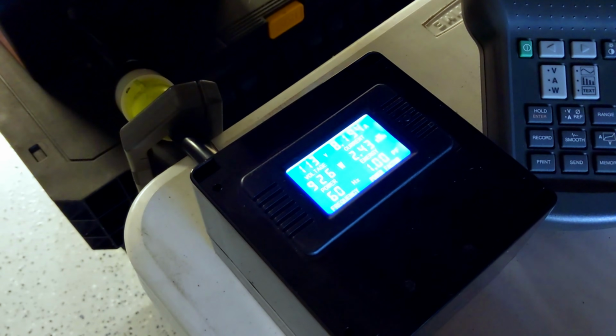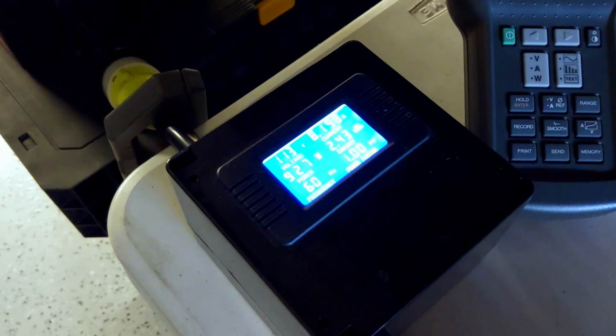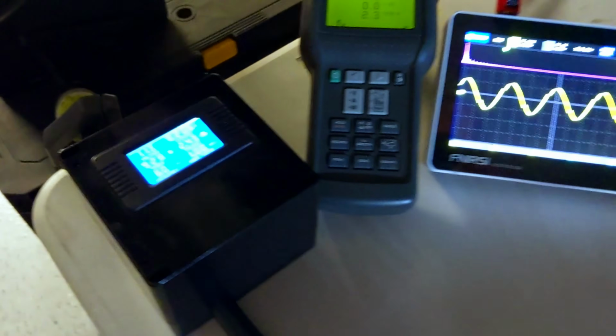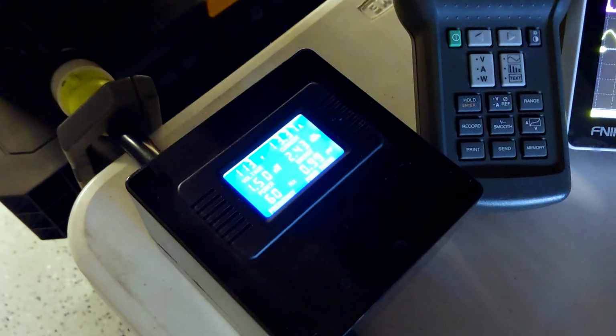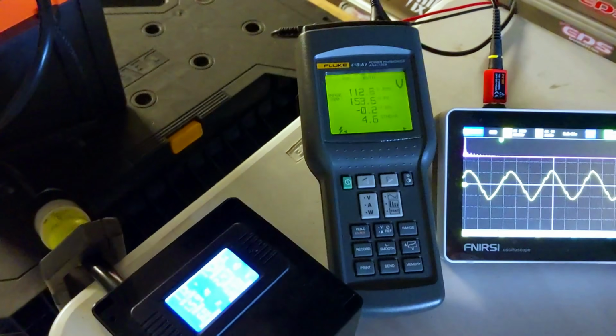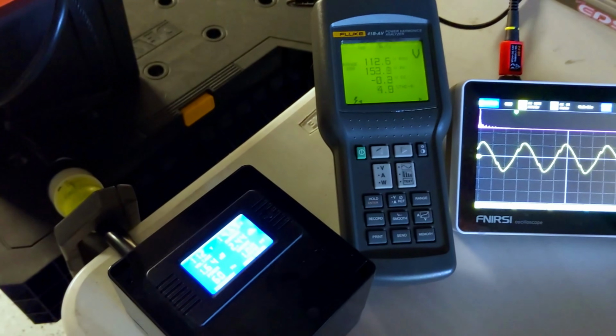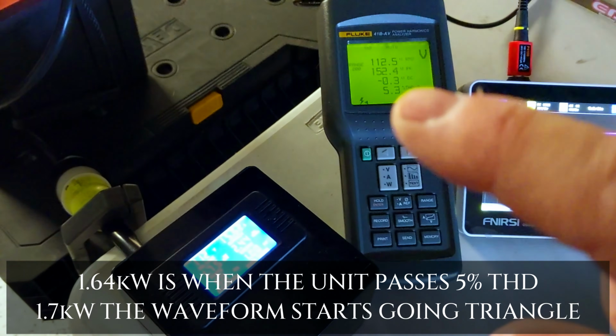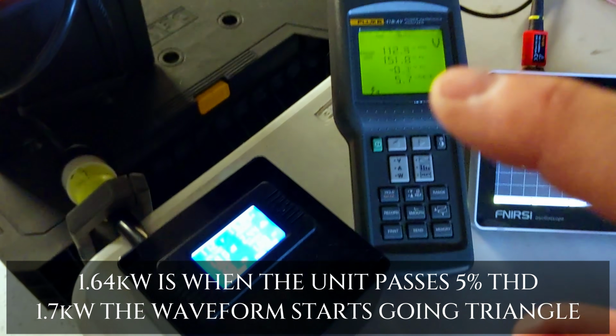All right, let's go ahead and take this up a notch. We're pretty much leveled out on this load bank setting, so we're going to kick this up quite a bit. Now you can see the draw increasing quickly. Ooh, at 1.6 kilowatts, we're already at 5% total harmonic distortion.